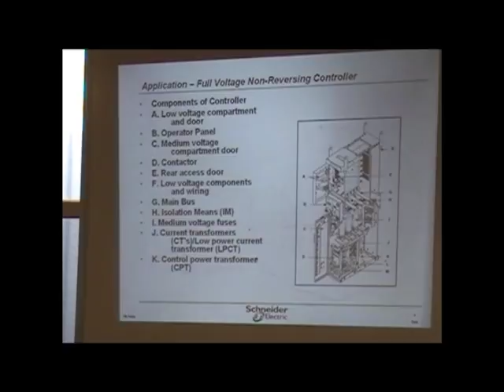But still, the fact remains that it's under load, so your equipment life is not going to be that high when you have that kind of arcing going across and everything. So you always want to minimize that. If you have no load, then when you open it, there should be no arc at all, essentially, or minimized arc altogether.